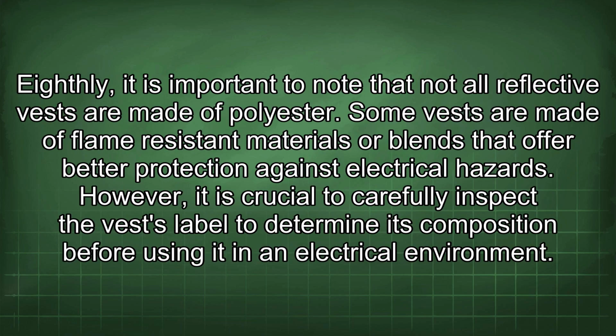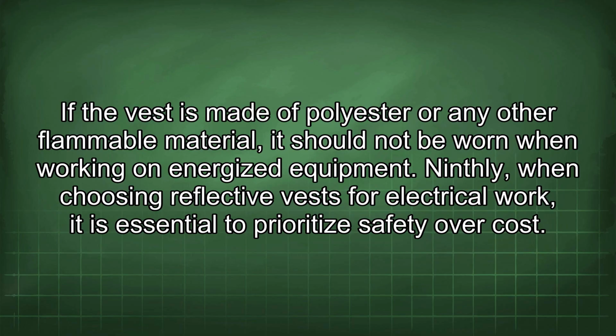Eighthly, it is important to note that not all reflective vests are made of polyester. Some vests are made of flame-resistant materials or blends that offer better protection against electrical hazards. However, it is crucial to carefully inspect the vest label to determine its composition before using it in an electrical environment. If the vest is made of polyester or any other flammable material, it should not be worn when working on energized equipment. Ninthly, when choosing reflective vests for electrical work, it is essential to prioritize safety over cost.